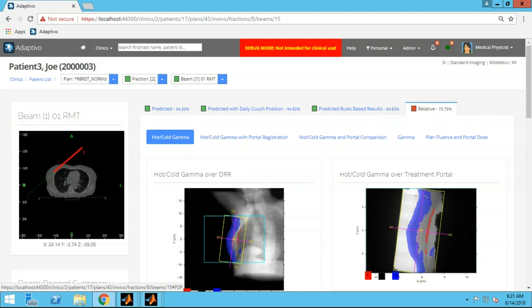What I like to point out with the relative comparison is: if you're only using relative mode, on day one you're hoping you're in the right position. On day two if you get a result like this, you don't know if you were out of tolerance on day one or if setup was wrong on day two — which one's right? Whereas with Adaptivo and the predicted image, right on day one you know if you're set up as you had planned, and you can proceed with confidence after that.